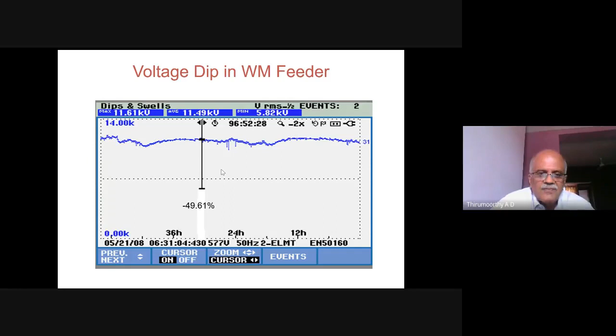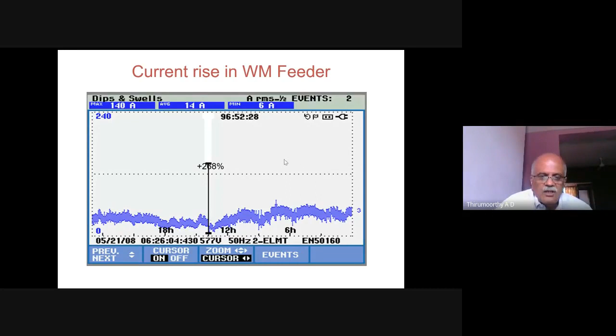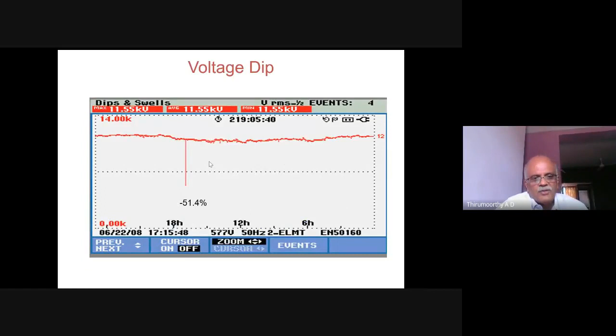And before that, you can see that there is a current variation of nearly 268% from the windmills that has been pumped to the grid. Sudden transient current that is pumped into the grid. So these are all some unwanted events that are occurring in the grid. You can see that there is a similar type of event. More than 50% of the voltage has dropped, and 40% of the windmills have tripped. And it takes nearly half an hour to 1 hour for the windmills to regain the original generation level.